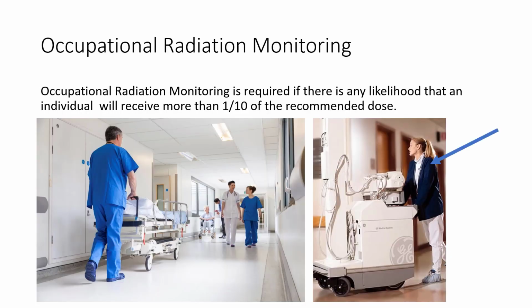Who is actually occupationally exposed to ionizing radiation in medical imaging? Occupational radiation monitoring is required if there is any likelihood that an individual, whether they be the radiographer, a nurse, etc., will receive more than 1/10 of the yearly recommended dose, or 0.5 rem.